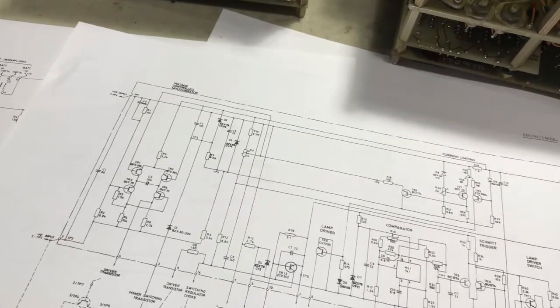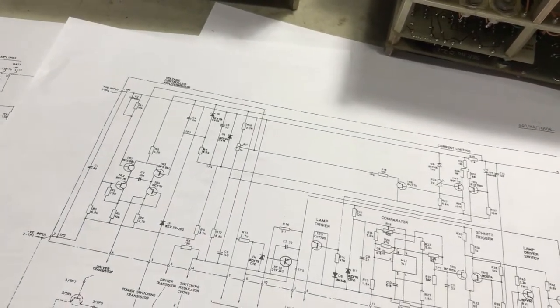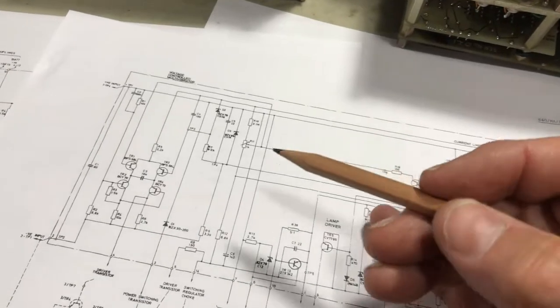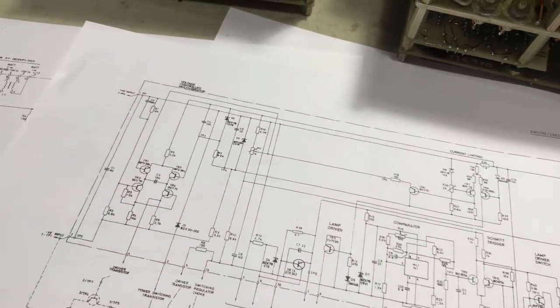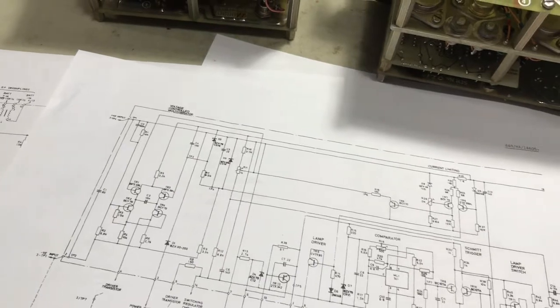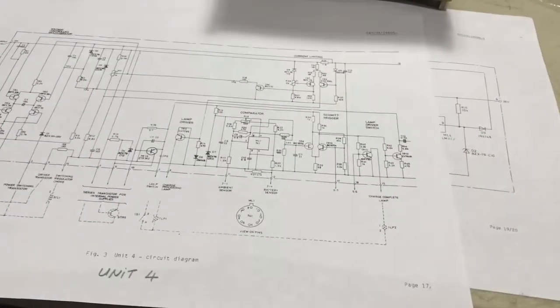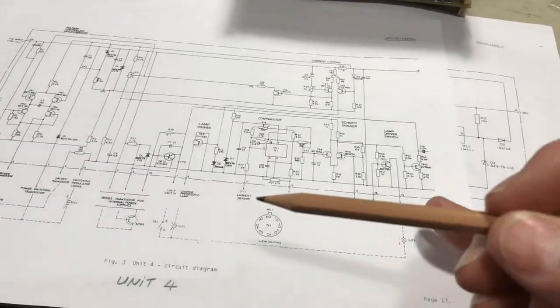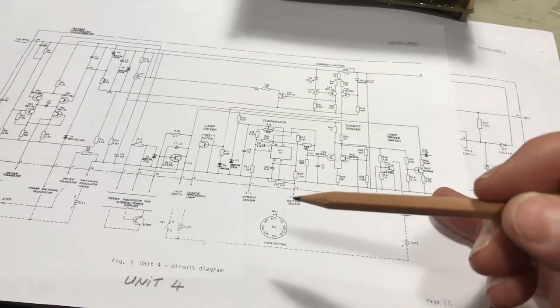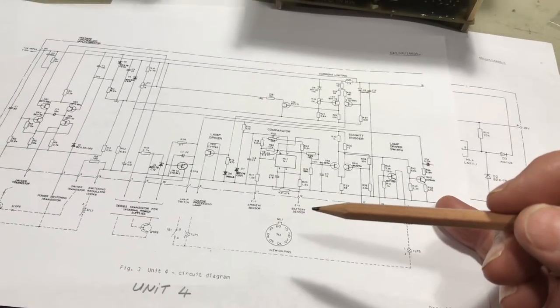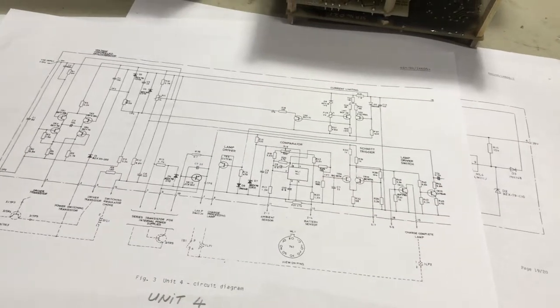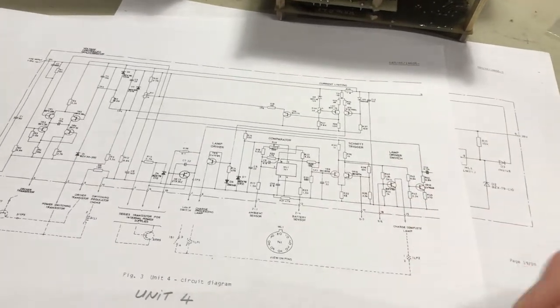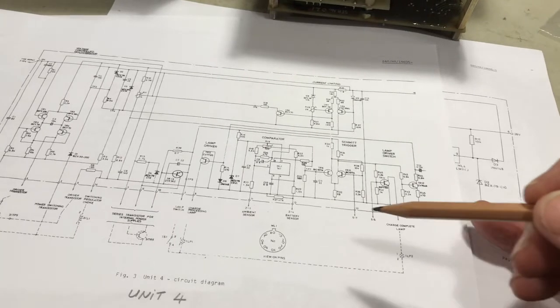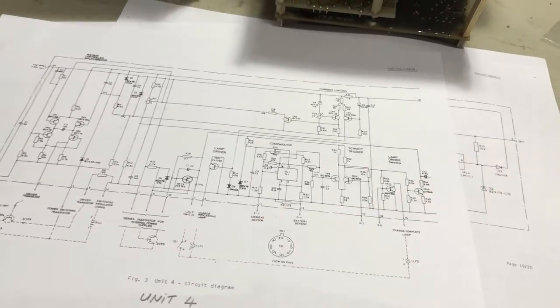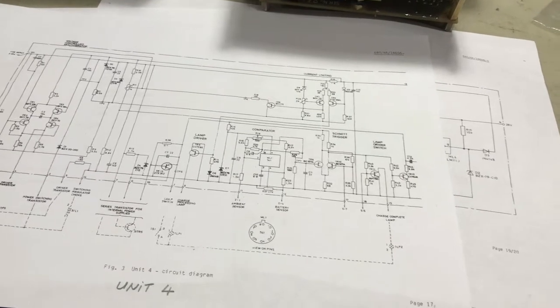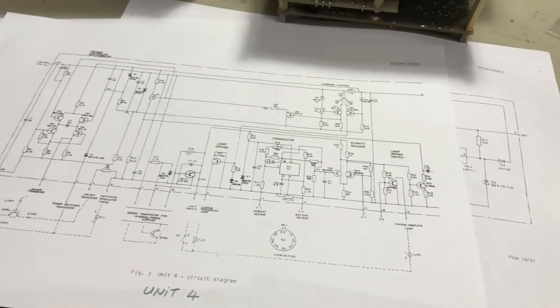The battery's still on charge, but it just doesn't march up anymore. That sets the voltage limit at 31.5. Probably 10 or 15 minutes later, as the temperature between ambient and the diodes within the battery case changes state, the comparator triggers a signal to the logic board, which operates the Schmitt trigger, turning off the battery charger and switching over the lights.